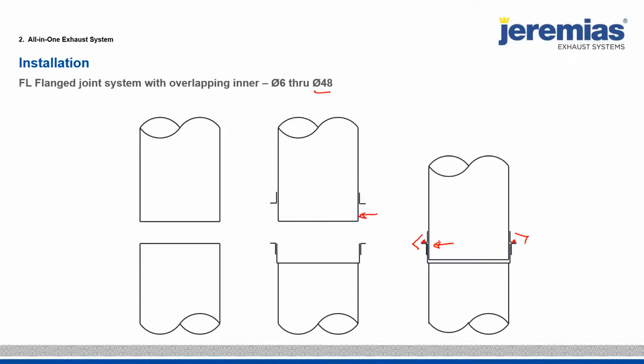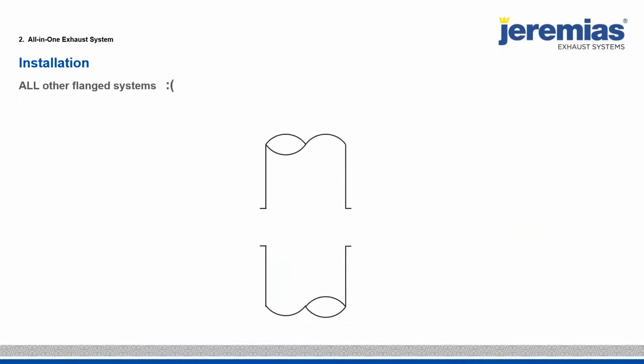So this is critical because we are seeing a ton of these stack systems, the American style flange systems, leak. Because you're putting the silicone on the flanges, the system goes together, and what you actually have is slight bridges that hold condensate, or the gasket itself is directly influenced by the condensate or high pressure steam washing on kitchen ventilation systems and so on.